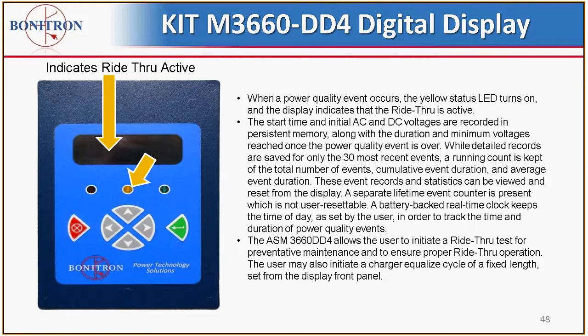When a power quality event occurs, the yellow status LED turns on and the display indicates that the ride-through is active. In other words, there's a ride-through event right now, the amber light is lit, and it's telling you that the unit is providing backup or DC bus voltage. When the ride-through event is over, it will turn off and go back to a static state.